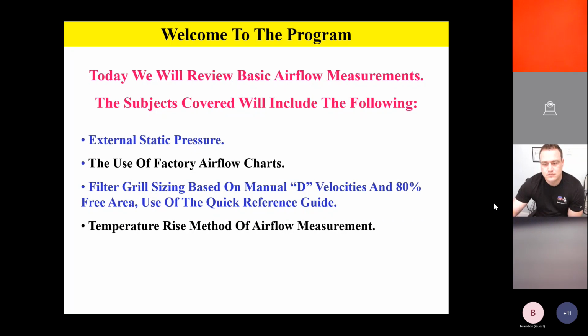Anyway, so filter grill sizing will be based on manual D. That quick sheet is based on manual D recommended velocities across the filter grill and 80% free area, and we'll use that quick reference guide I just made reference to. And finally, towards the end of our training session today, we're going to review a temperature rise method of airflow measurement as well. It's just a quick little application of some math and a temperature probe, and we'll show you how to do that as well. So to summarize, today we're going to be learning how to measure airflow 2 different ways. After today, I would hope that everyone will be equipped and ready to measure airflow at least 2 different ways.